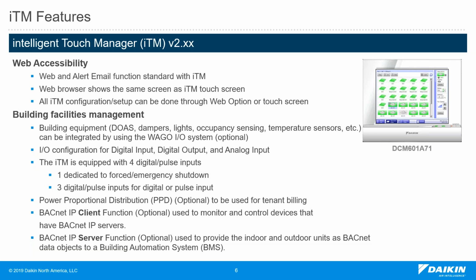From the building facility management side, there is a different way to integrate other equipment to the ITM. So if there is a lighting system, dampers, occupancy, temperature sensor, humidity sensor, all of those can be added to the ITM. There's multiple ways to do it. We can add a Daikin DI/DIO board that you can connect those sensors or the equipment to. Then this Daikin DI or DIO board can be connected to the ITM directly, or there is a Wago IO system that can do the same thing as well.